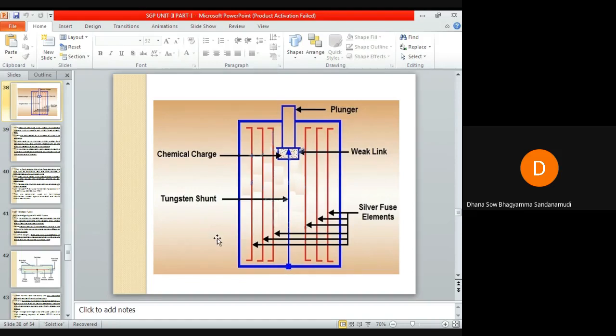So when a fault occurs, first of all, the silver fuse elements are the first to be blown out, and then the current is transferred to the tungsten wire. The weak link in series with the tungsten wire gets fused and causes the chemical charge to be detonated, which means they just explode. These chemical charges will explode, and this will force the plunger outward. So when the plunger is pushed outward, the circuit breaker will operate.